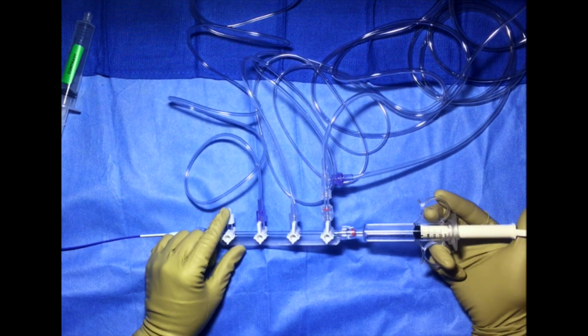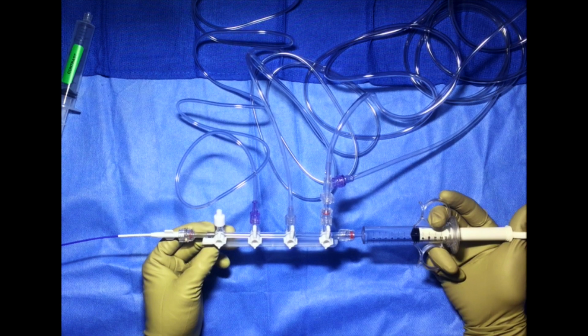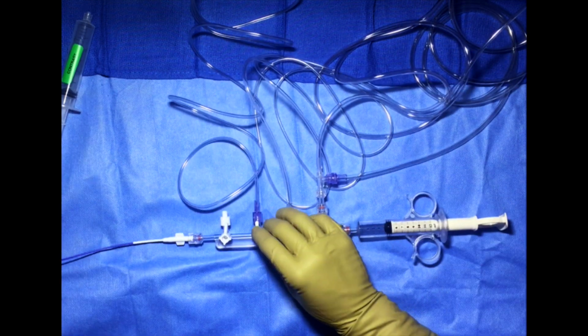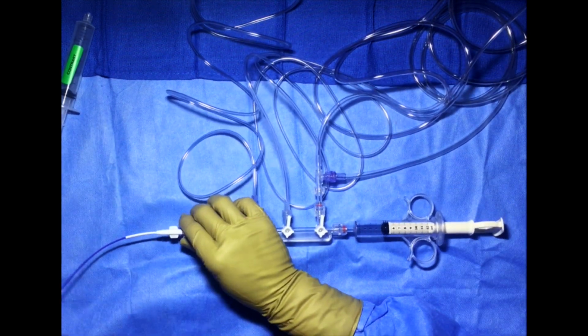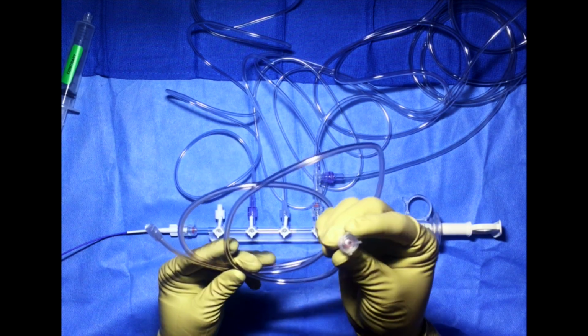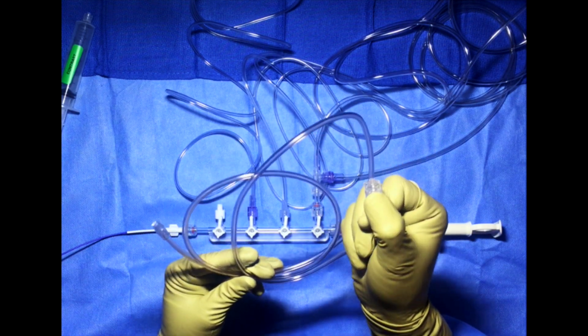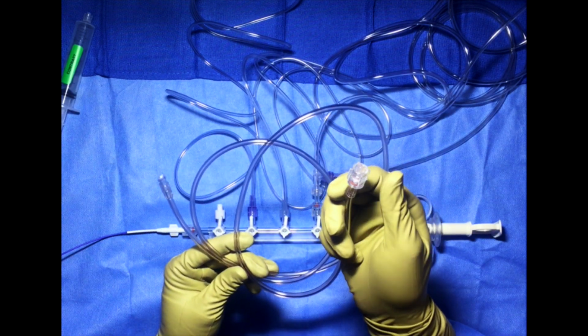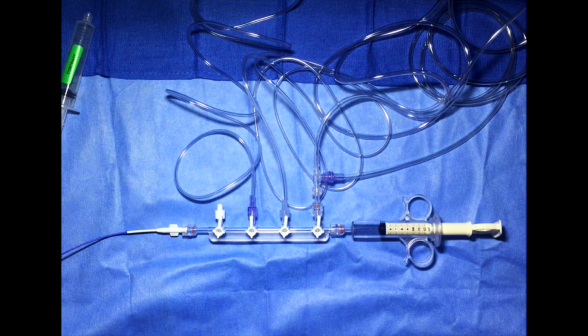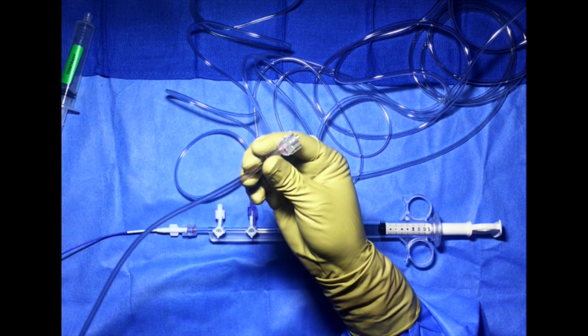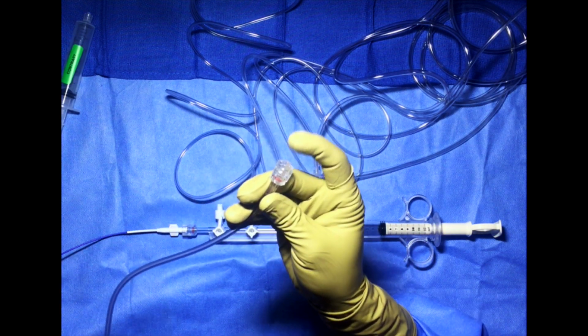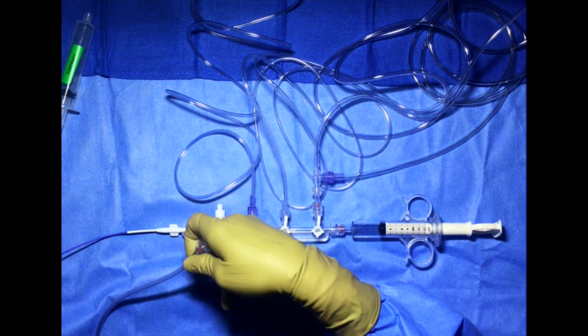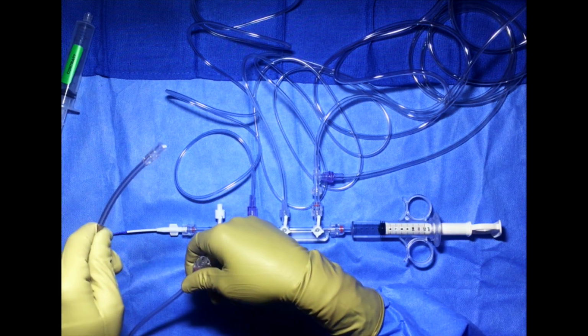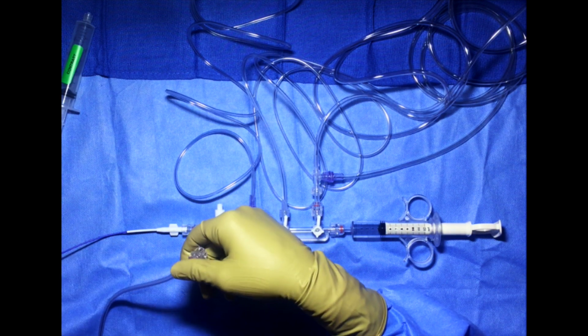Technically, if you're clearing out the transducer, you could push through here. There's also going to be another thicker tubing that has this rotating hub. If you see this, it's probably going to be hooked to something that needs to rotate. So a catheter. This stuff's pretty stiff. You want to stretch it out a little bit. So this is that high pressure tubing. We're going to keep this end because we're going to connect it to the catheter. This other end is going to go off the table to whoever's at the power injector.